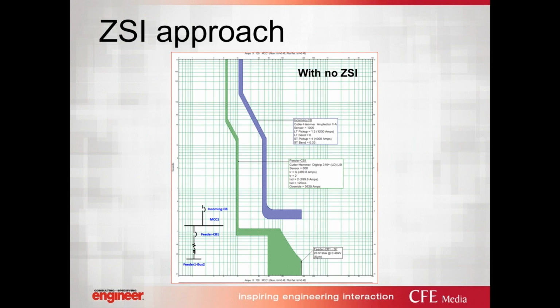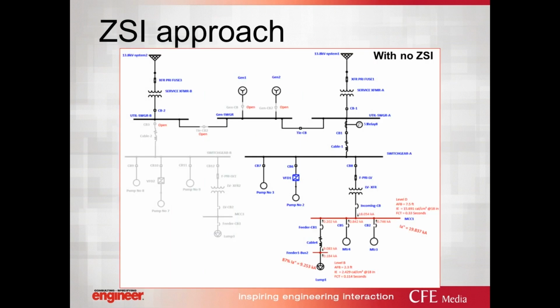The picture that you see here, the incoming breaker and the feeder breaker with no ZSI. Typical coordination, we all as engineers, what we do, make sure the coordination exists. Now we're trying to make a coordination, which is fine. We have a coordination. Now let's look into incident energy for this system. This is the incoming breaker to one of these feeder.